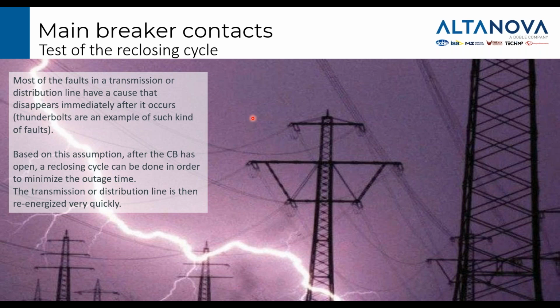Inside the springs of the circuit breaker there should be enough energy to guarantee a reclosing cycle, because in case of fault, at least one attempt to reclose the circuit breaker must be made. For example, if the fault is a lightning strike, once the lightning touches one of the towers, immediately after it disappears. So the default is to at least try to close the circuit breaker and put the line in service once again. So in this situation, the circuit breaker must open and close after, let's say, 500 milliseconds, and all the energy must be stored inside. There is no time to wait for the motor to charge the springs again.